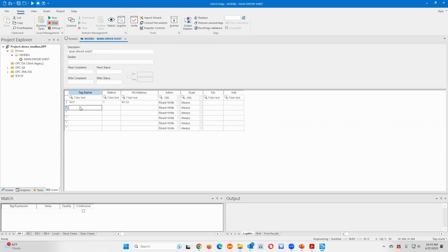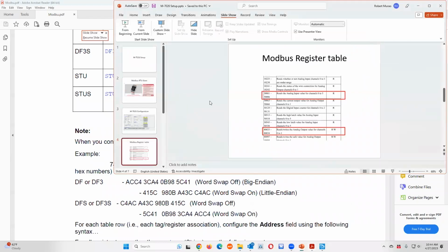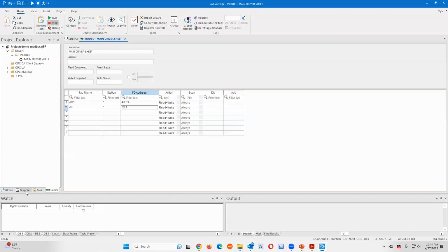If I wanted to do an analog input tag, I do AI. Actually, I'm sorry, that should have been 0, but that's okay. We'll just create it now. 1, and this is a 3x, and then :1, based on the Modbus register table, which is this slide right here, which is up here, 30,001. Back here. And if we wanted to create a graphic, we can come back here. Actually, I want to save this first. Right click and save.